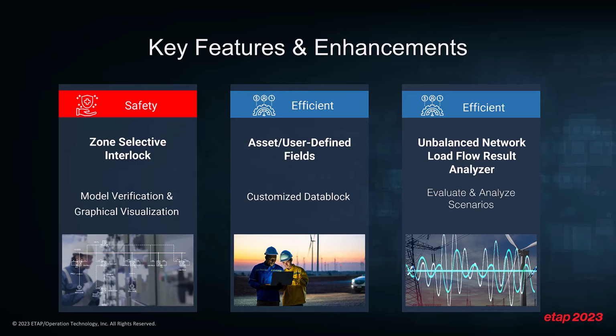Previous ETAP releases also included the ability to add user-defined fields in order for you to build and maintain an electrical maintenance plan in compliance with NFPA 70B and other local regulations. It allows you to also ensure the safe and correct commissioning of devices by including fields that are usually not part of a typical selectivity study, such as thermal settings for low voltage trip units. These user-defined fields can now be enabled as part of the ETAP data blocks, allowing you to print diagrams for engineering, operations, maintenance, protection as needed by simply applying custom data blocks with unlimited custom fields per asset.